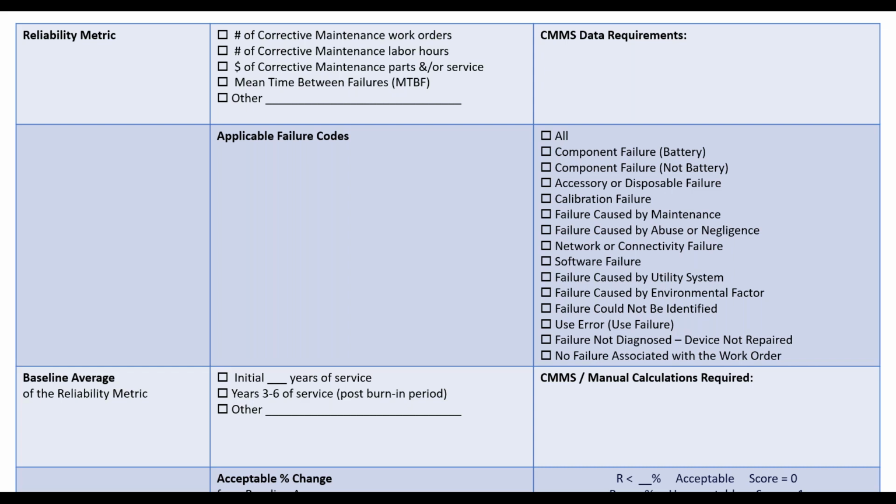Agreed. So you're measuring the ongoing average every year, but you have to have something to compare that to know if your trend is going up or down. So that's why we want to have maybe a 3-year window post warranty. Let's just say in your example, the average number of labor hours for that particular equipment type is 25 hours per year for those 3 years post warranty.